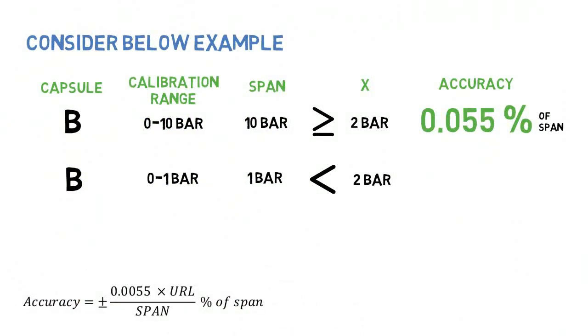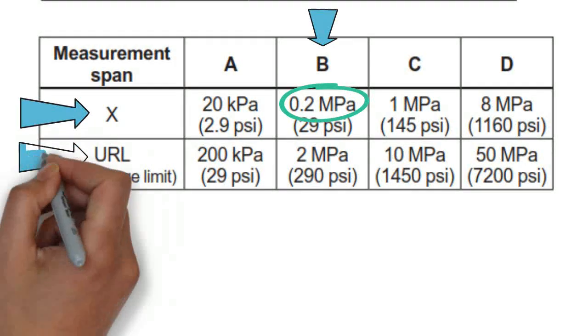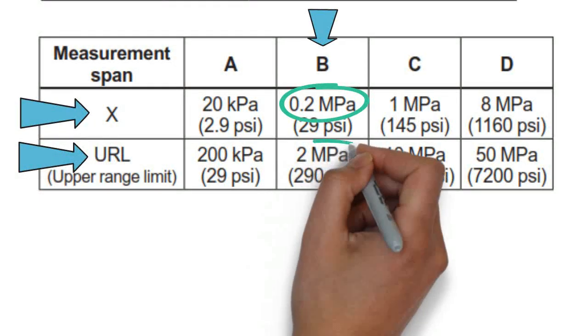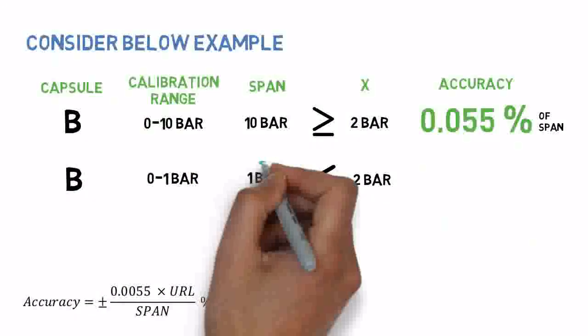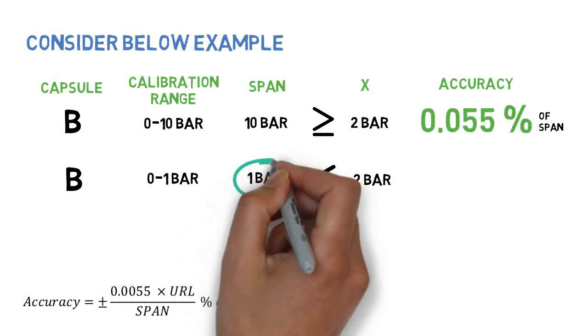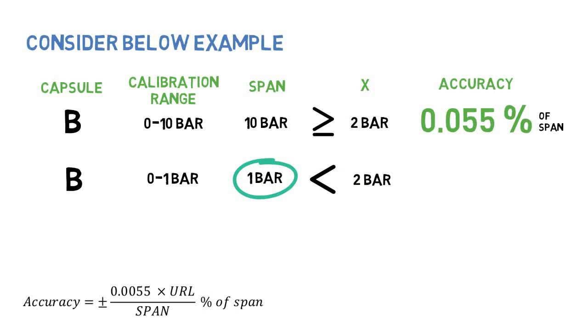For example, URL for capsule B is 2 MPa or 20 bar. Substituting URL and span value of this example into this formula, accuracy is 0.11% of span.